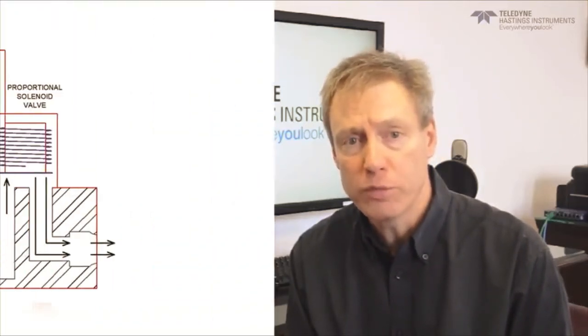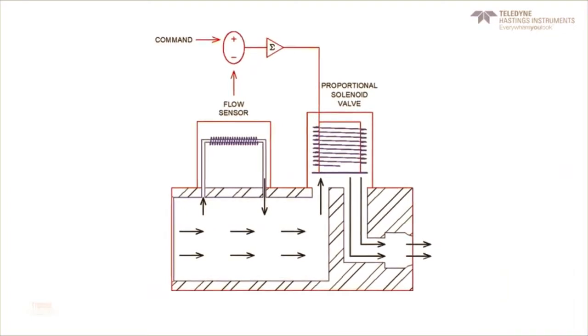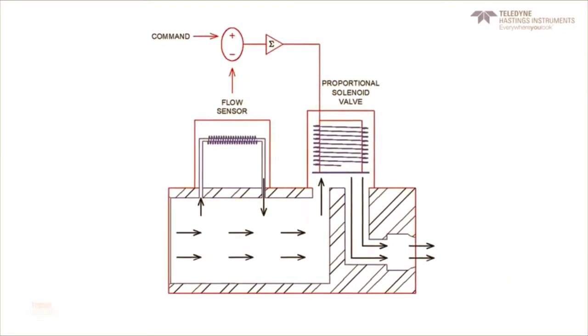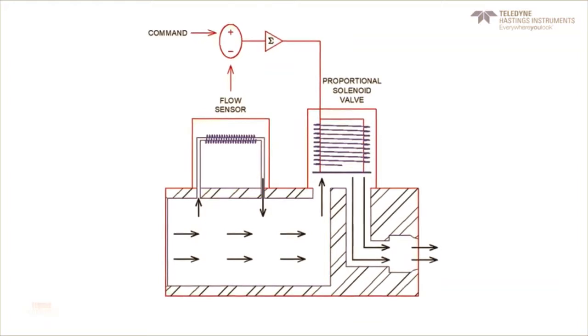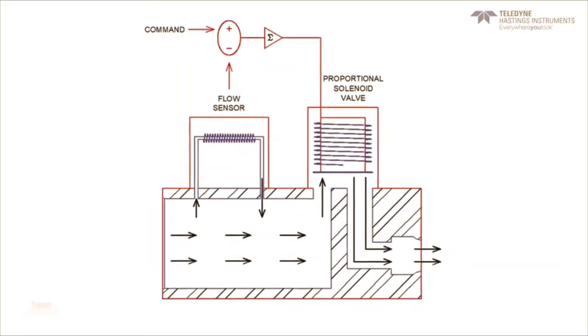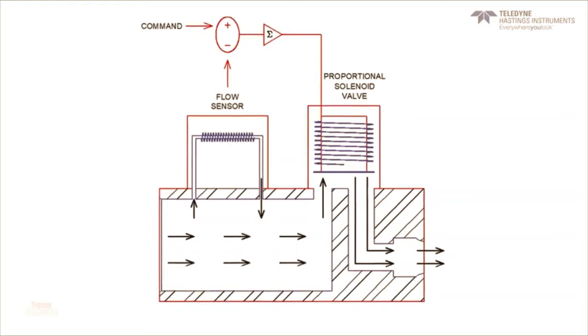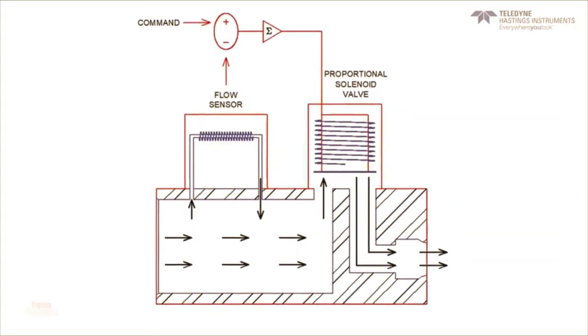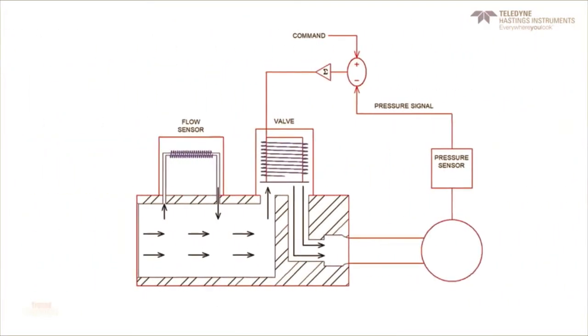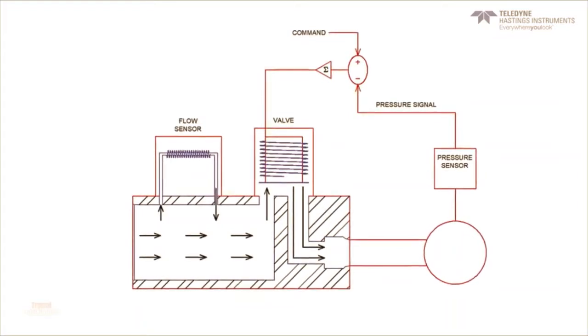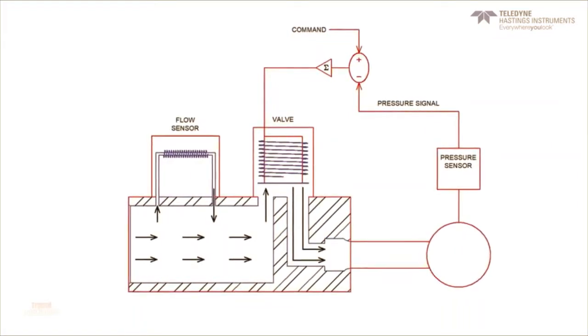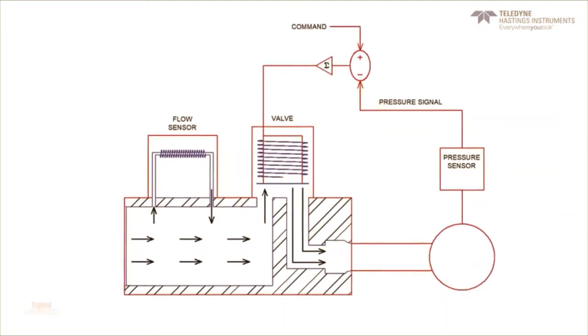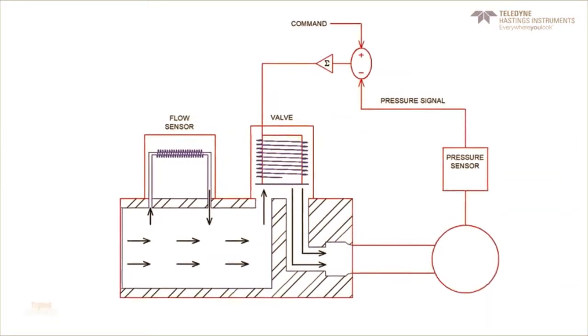Now, many viewers probably already know that a flow controller measures flow and then compares the flow measurement to the user's set point command. Then internally, the flow controller decides how to adjust the proportional solenoid valve. So, in the flow control mode, the flow signal is the feedback in the control loop. But now here's the cool thing. We can use a pressure signal as the feedback instead of the flow signal to control the valve. In this mode, the instrument becomes a pressure controller. So now let's take a look at how that's going to work.